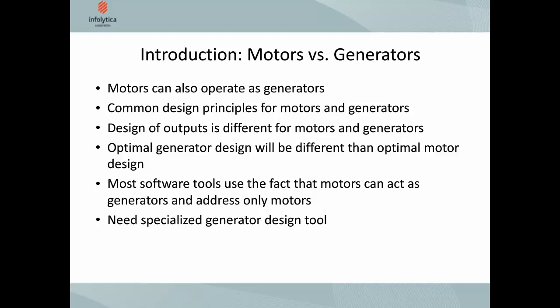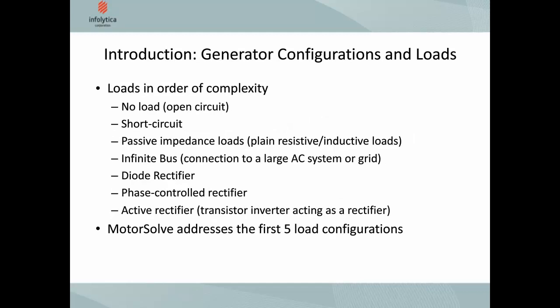What are some of the configurations and loads we see with generators? There are about six or seven different types. The simple ones are no-load or open circuit, used mostly for testing purposes, and short circuit — those two basic loads can characterize the generator. The third type is a passive impedance load, which can be purely resistive or a combination of resistive-inductive or resistive-capacitive loads.